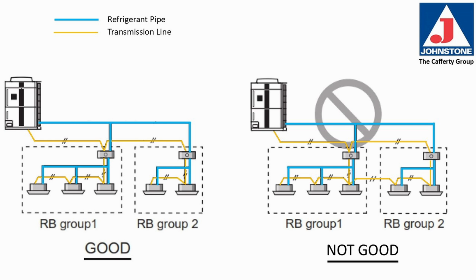In this example, you'll see the good design on the left. RB group number 1 has 3 indoor units that are wired together, they pipe together, and they connect to the same refrigerant branch. RB Group 2, we have 2 indoor units connected together with refrigerant lines to the one RB box. For the bad side, you will see that all of the indoor units are daisy-chained together. We can only have the communication circuit connecting where the refrigeration circuit that runs to that unit is connected. By putting the jumper wire between Group 1 and Group 2, that's telling the system that there's really only one group there and it doesn't know which valves to open when a unit is calling.